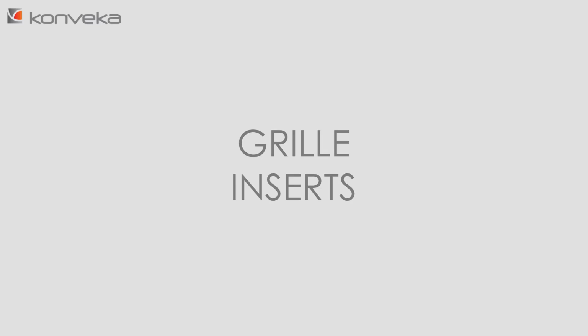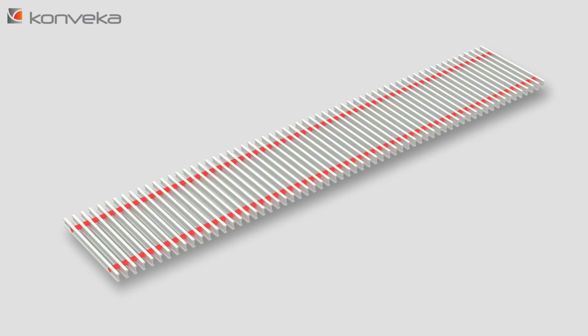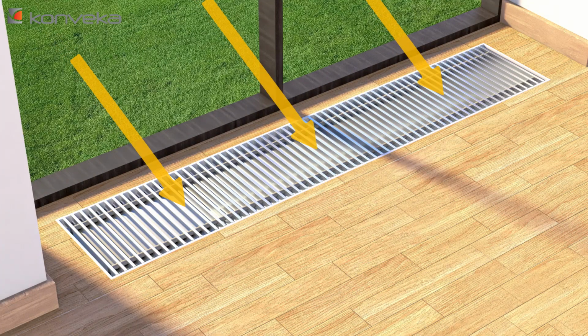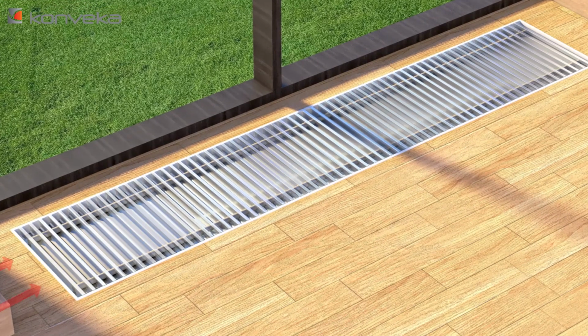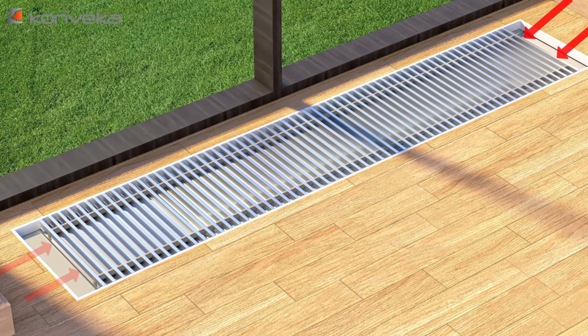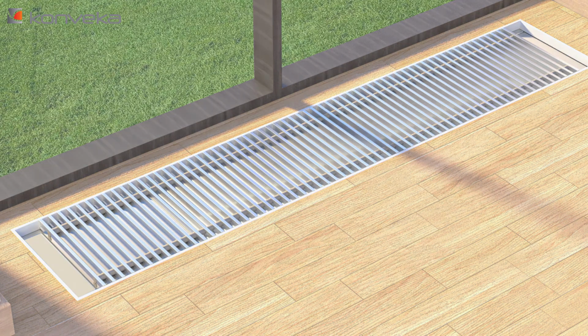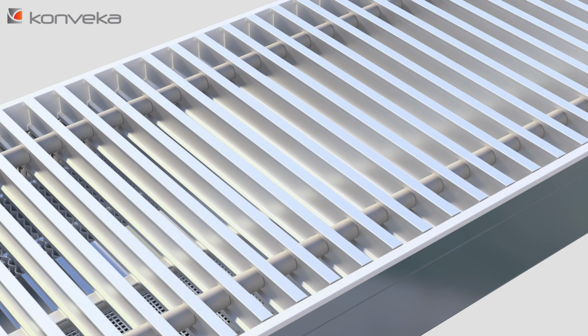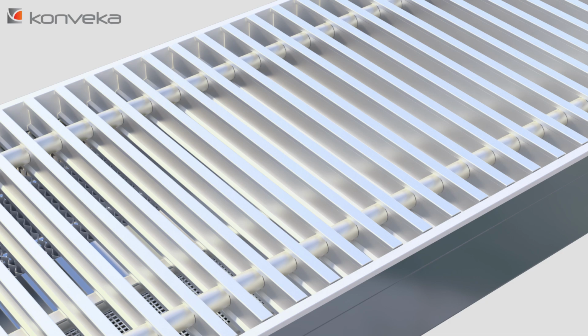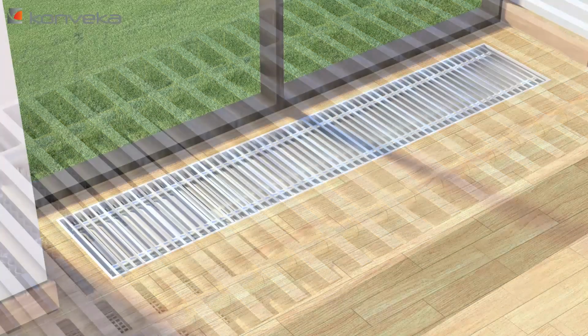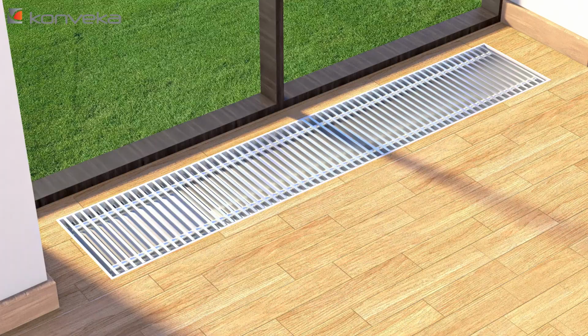Grill inserts. Very often, grill inserts are made of plastic. Experience has shown that plastic inserts exposed to heat and UV radiation will shrink over time. As the inserts shrink, the length of the entire grill decreases, so that after a while the ends of the convector become uncovered. Besides this, UV radiation produces fading in plastic inserts, so their color becomes different from the color of the grill over time. This problem was solved by using aluminum inserts instead of plastic. Aluminum inserts are heat-resistant and UV-resistant, and thus retain their dimensions and color throughout the entire service life.